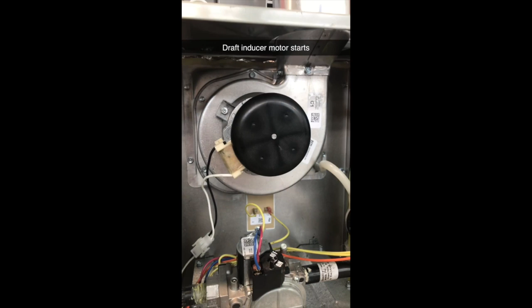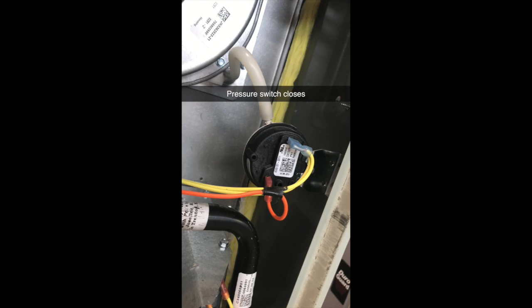Step number 2 is the draft inducer motor starts. Step number 3 is the pressure switch safety circuit closes. Step number 4 is hot surface igniter warms up, followed by pre-purge.